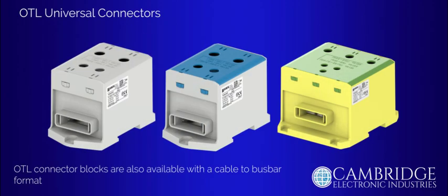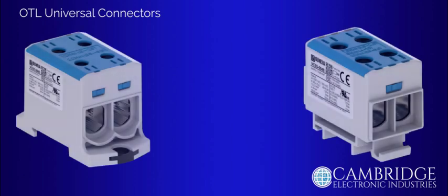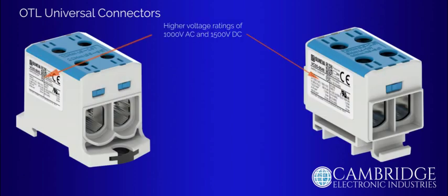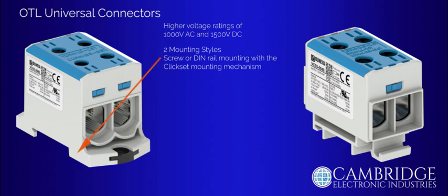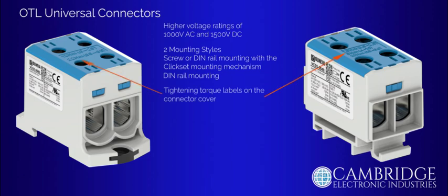OTL connectors are also available for a cable to busbar solution and are available in grey, blue and green-yellow colour housings. The key features of all styles of the OTL connectors include higher voltage ratings of 1000 volts AC and 1500 volts DC. There are 2 mounting styles available. The customer can choose between the screw or DIN rail mounting block, which features the click-set mounting mechanism, or the standard DIN rail mounting. The tightening torque for each size of cable is clearly labelled on the connector block shell.